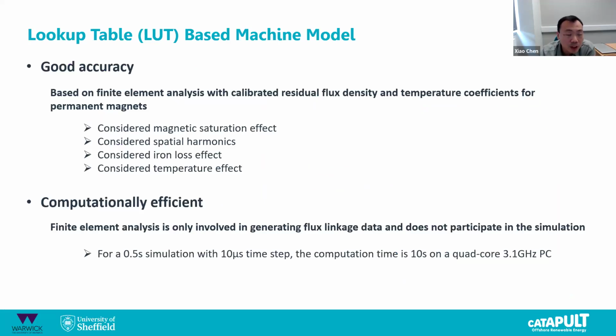So a bit of a summary of this type of model: we can have good accuracy because we are based on the finite element analysis. In the finite element analysis, we also calibrate the residual flux density, and also the temperature coefficient, based on the measurements, and also measure the temperature coefficients of the magnets.